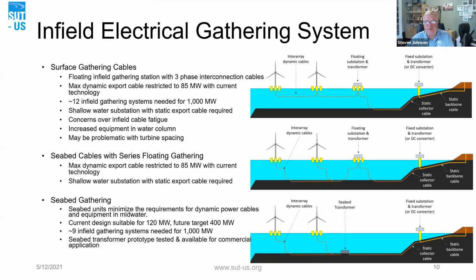One of the problems with the floating substation, there's an export cable here which becomes a bottleneck. At the moment, the largest power cable installed in what we call dynamic mode, because as the vessel moves the cable moves, it's all dynamic, is NKT's unit at 85 megawatts. So that becomes a bottleneck, restricting us to what the export cable can handle, 85 megawatts, and as we go subsea, once again, 85 megawatts.